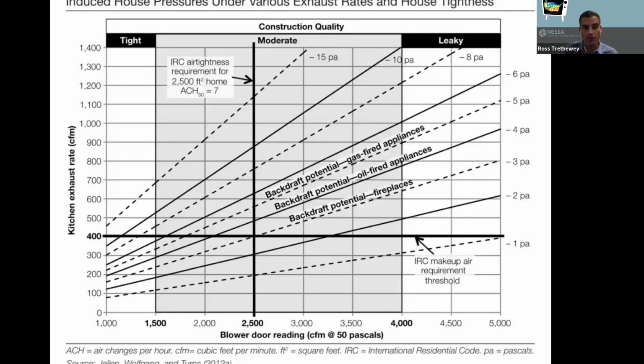If you look at the 400 CFM exhaust requirement on the vertical axis, that's the black line, you can see where they meet. Anytime you're going to have an exhaust rate higher than 400, even in a 7 ACH 50 house, you have a risk of backdrafting. So if I had a 600 CFM hood without makeup air, I'm most likely going to backdraft gas-fired appliances, oil-fired appliances, and fireplaces in that kind of configuration. It's a nice chart to get a feel for, based on the air tightness of your building, how risky it is without makeup air to offset the pressure differential that might be generated in your house when you run your kitchen exhaust fan.